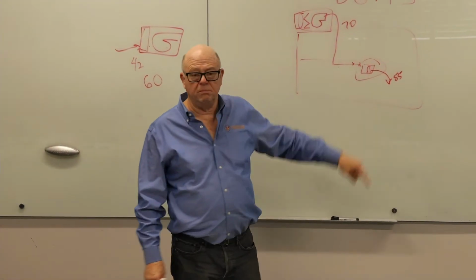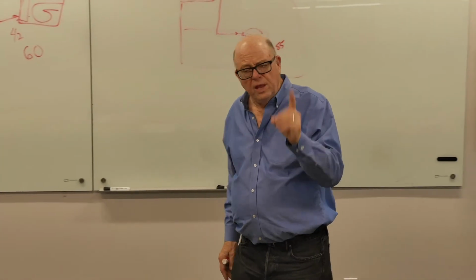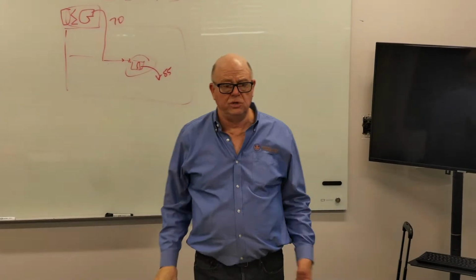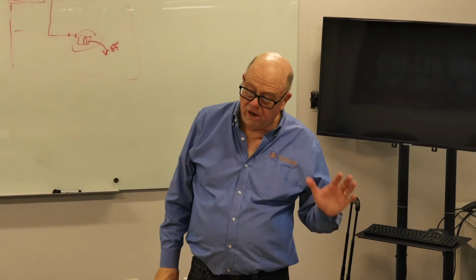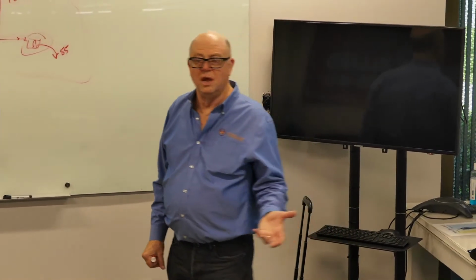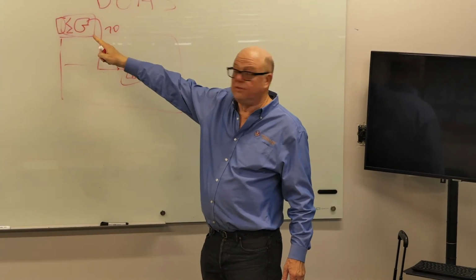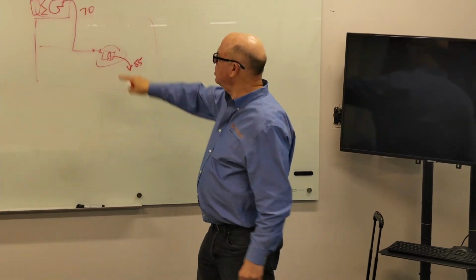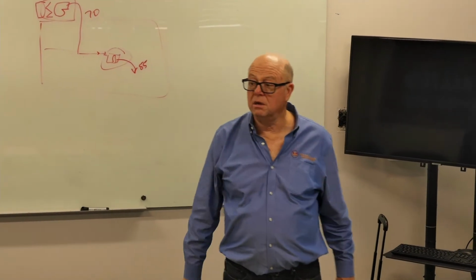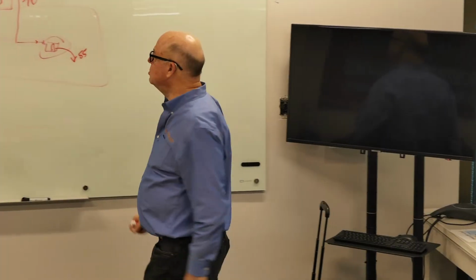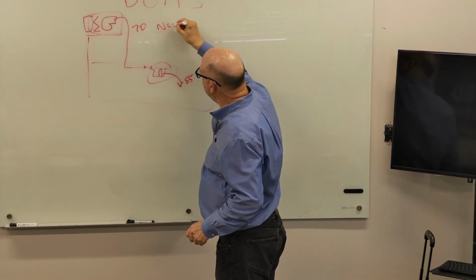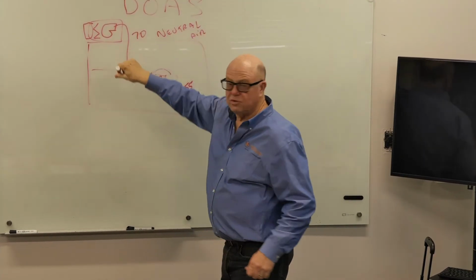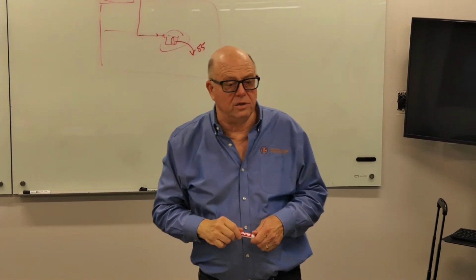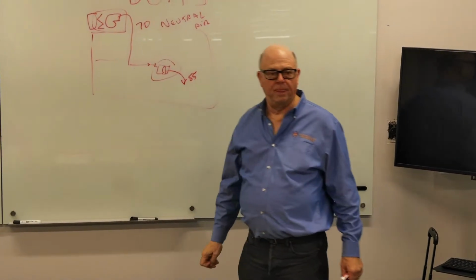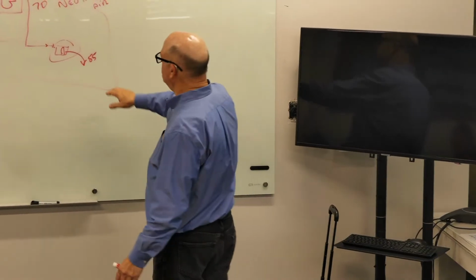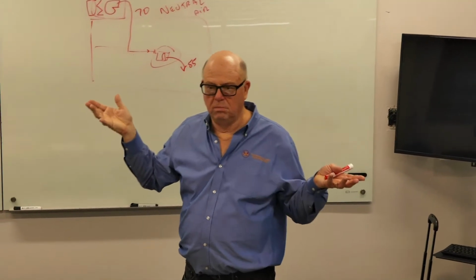This is an outside air duct. You didn't insulate it, and as long as you don't cool it down below the point where you'll get condensation, you don't need to. Now, I freely admit that I can't anticipate every single case. There may be a time when you need the extra cooling from this thing to make the rest of it work. But if you do, you're going to have to insulate this duct like it was a supply duct. And so generally speaking, the term we want is neutral air from a DOAS. And the same thing in the winter. If it's 45 degrees outside, 70 is also a good number, because that's approximately the temperature that you're maintaining in the room. Okay? DOAS.